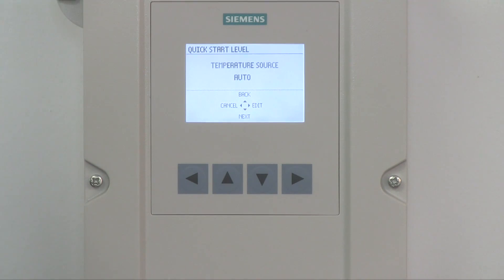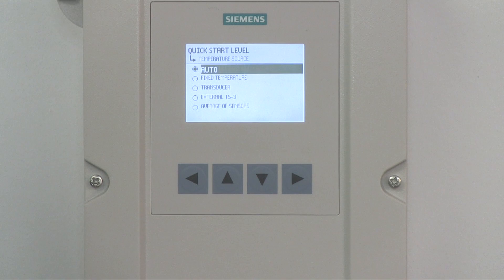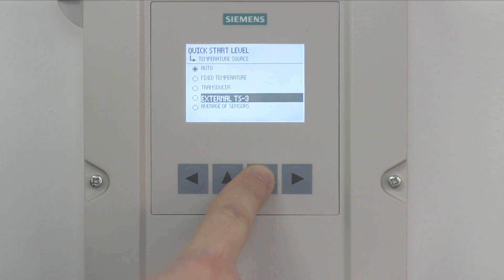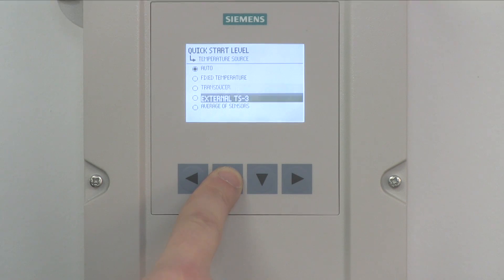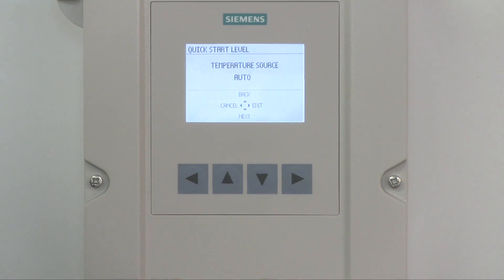Now let's select your temperature source. Press the right arrow to select Edit to change the temperature source. As the speed of sound changes with temperature, it's critical that we know the ambient temperature in the process to achieve an accurate measurement. The default temperature source is Auto. Using the up and down arrows, highlight your temperature source. If temperature changes quickly in your application, please use the TS3. It has a faster response than the transducer internal temperature sensor. Press the right arrow to enter your selection. Press the down arrow to select Next to proceed.